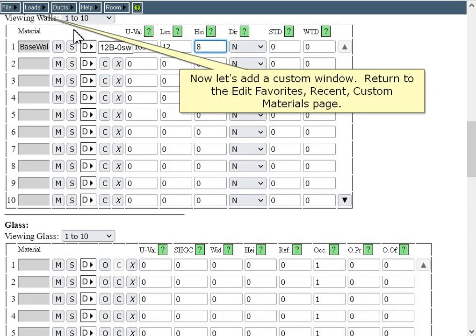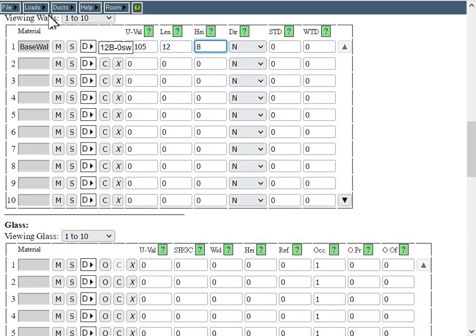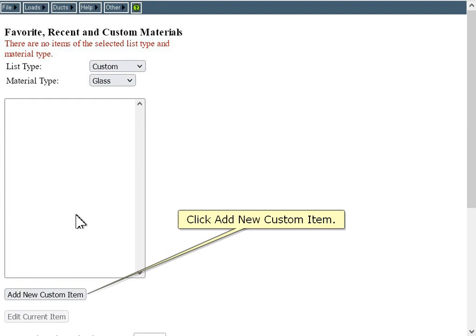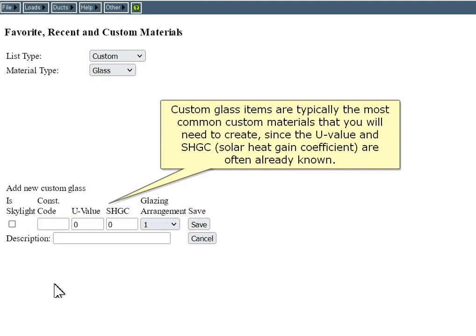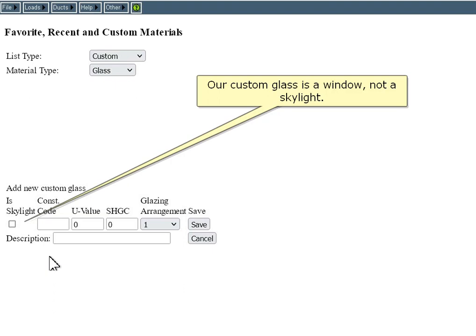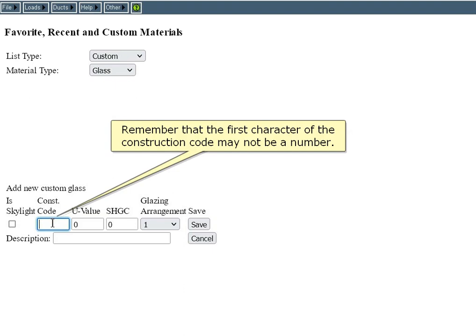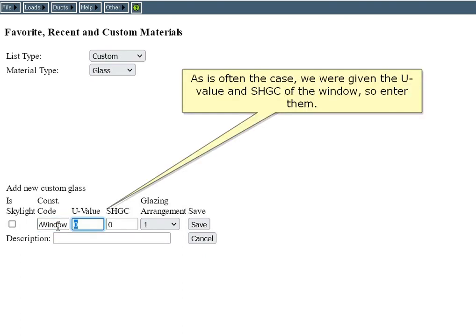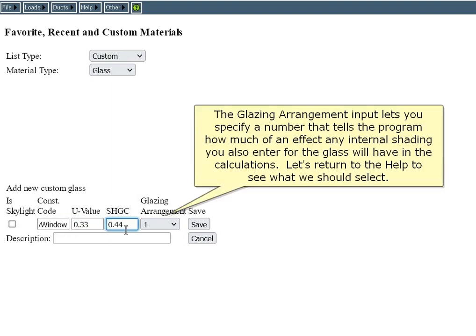Now let's add a custom window. Return to the Edit Favorites Recent Custom Materials page and change the material type to Glass. Click Add New Custom Item. Custom glass items are typically the most common custom materials you will need to create, since the U-value and solar heat gain coefficient are often already known. Our custom glass is a window, not a skylight. Remember that the first character of the construction code may not be a number. We were given the U-value and solar heat gain coefficient of the window, so enter them. The glazing arrangement input lets you specify a number that tells the program how much effect any internal shading you enter for the glass will have in the calculations.